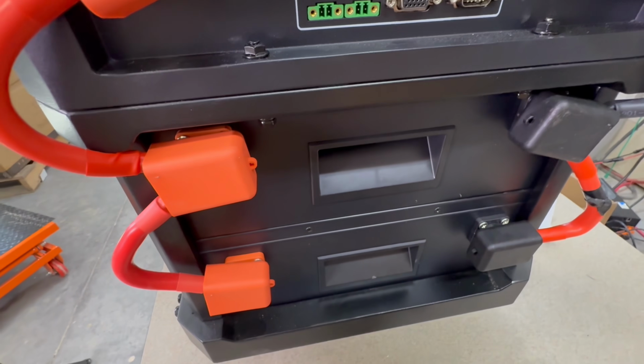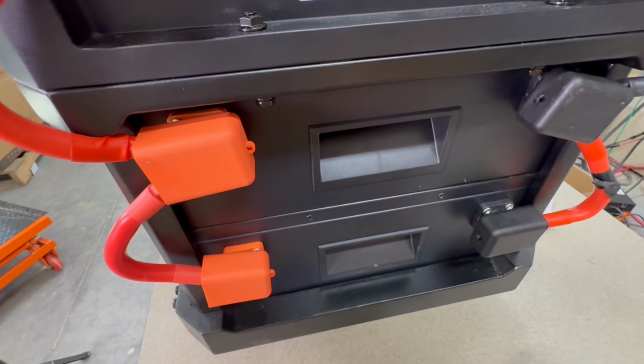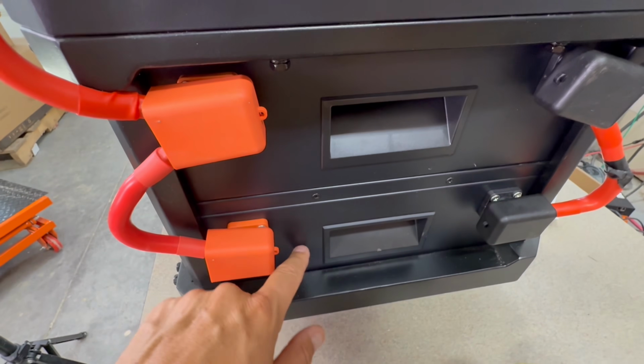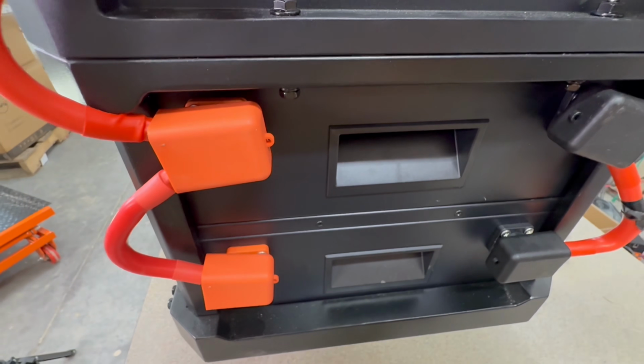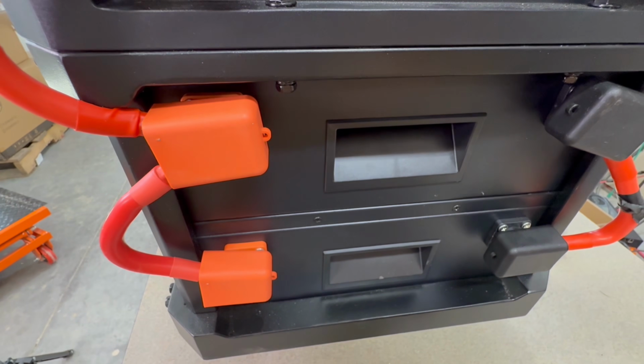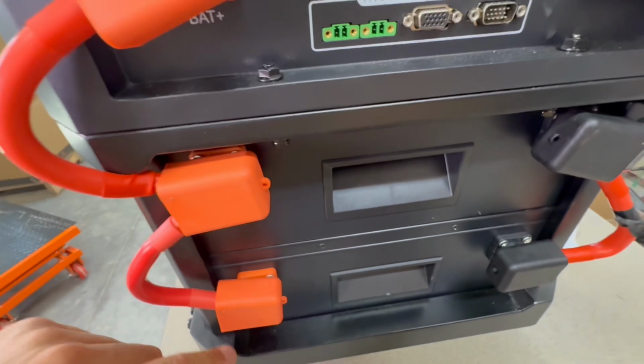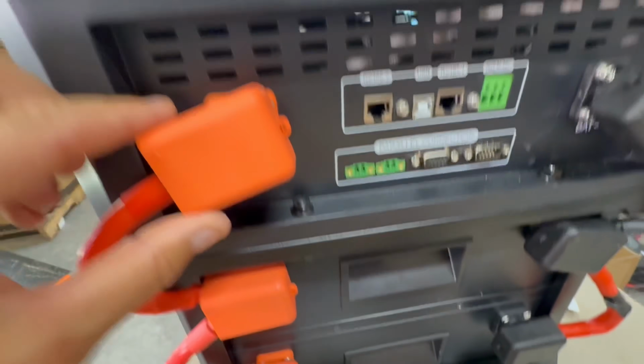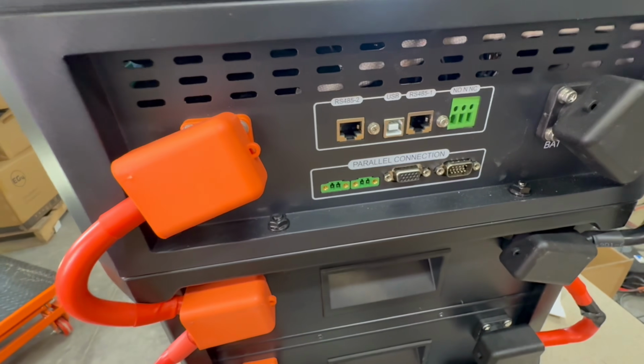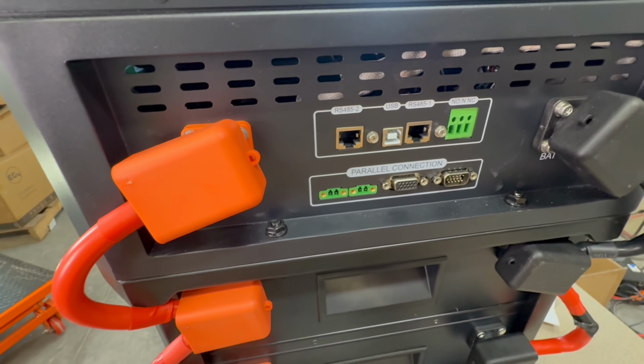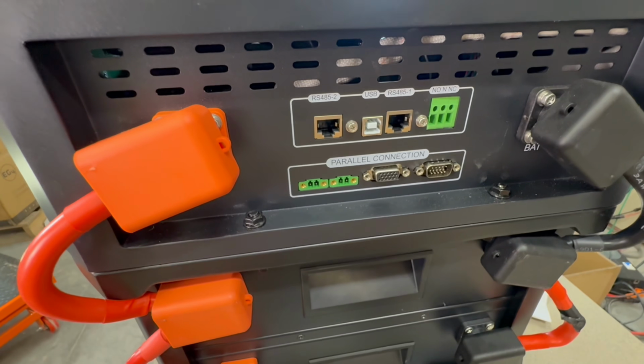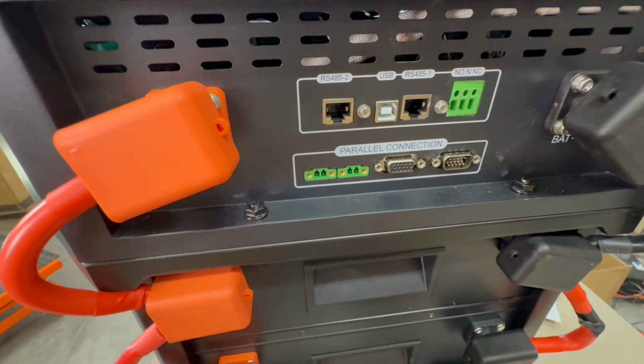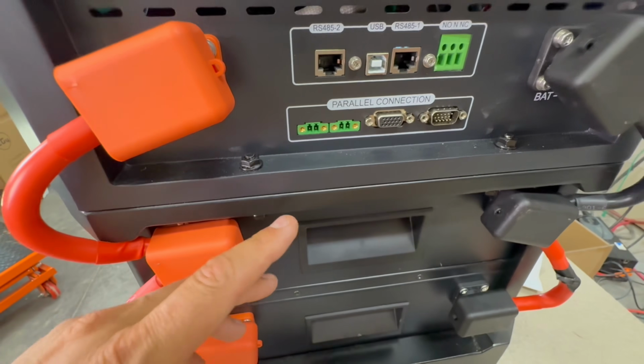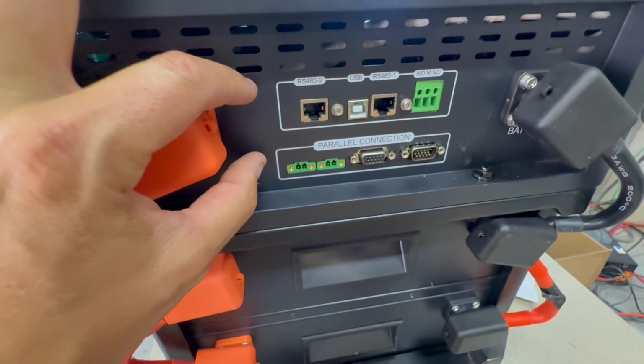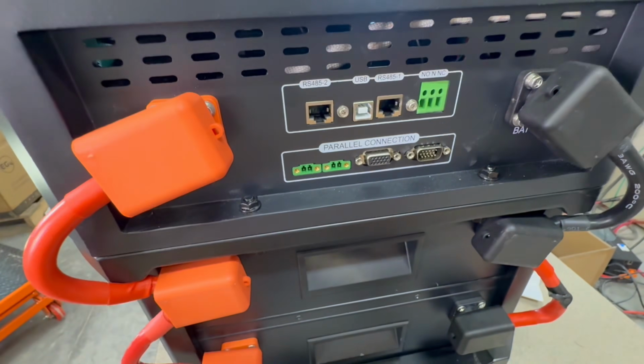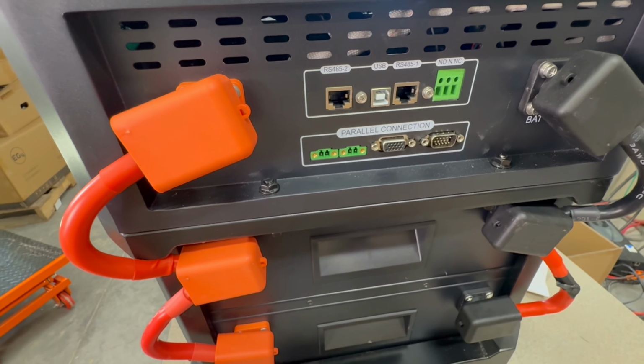My main issue on this side is the fact that it does not have overcurrent protection. We're relying on the BMS. The BMS on both these batteries has under voltage, over voltage protection, all that. But you need a breaker in between here. Of all places to put a breaker, it wouldn't have been on the PV side. There's a lot of different all-in-one inverters that still don't have a PV disconnect and certainly don't have a PV breaker, but this does, which is really odd to me. Like, why not put a breaker over here for the batteries? That is such an odd design.